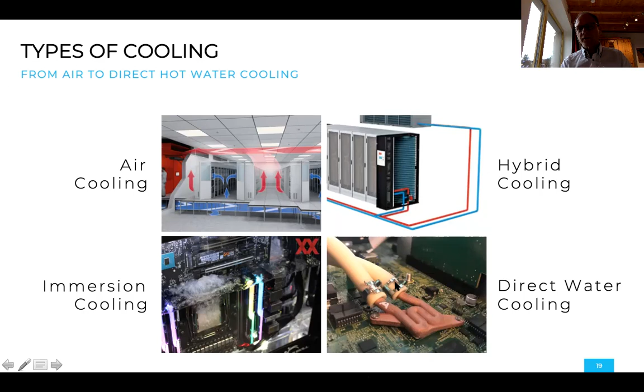And then, of course, you need a pump and a pump group, a redundant pump, and a heat exchanger to have a server rack where a circulating water loop is generated to cool down the servers. And this heat can now be extracted, and it can go to the building. It goes to a buffer tank, for example, and this buffer tank can be hooked up to the floor heating, or to the warm water supply of the building. And if this buffer tank is fully filled because the heat is not needed in the building, this warm water comes back here. And if it's too hot, you switch this motor, and then the hot water goes outside to a dry cooler in a closed loop circuit, and the hot water is cooled down to a level that's acceptable for the servers.